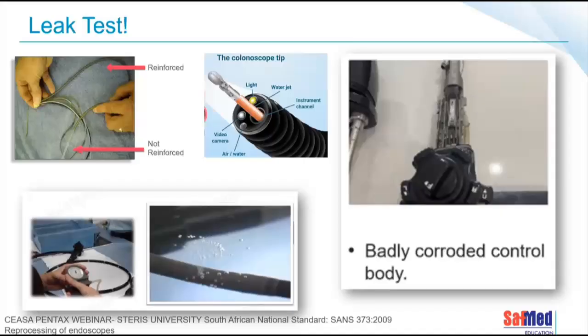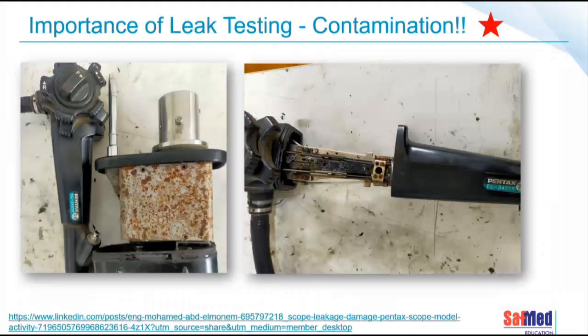Let's have a look at some of those images. To prevent damage to the scope, an important thing that we need to do is to do a leak test. With the leak test, we're pressurizing the scope to see that that biopsy channel is intact. If there's a hole in that, once we submerge the scope into some form of liquid, there is a good chance that that liquid itself, whether it's detergent, whether it's patient contamination, whether it's feces, whether it's gastric solutions, can all end up inside of our scope.